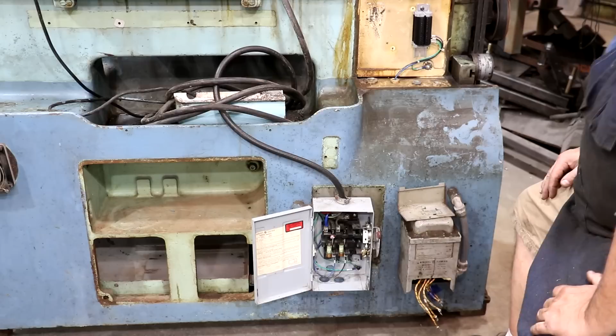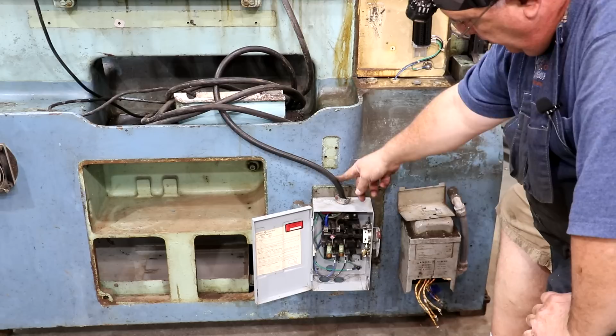All right, let's get these wires pulled. Step one: power comes into the power cord, goes to the fuse block down here. This is the main fuses for the whole system, and the disconnect where we can turn things on and off. Coming out of the bottom we have line 1 and line 2, my two hot wires for 220 volt single phase power.